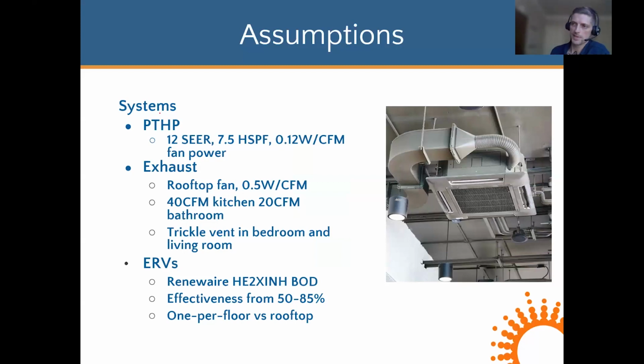And then we applied some systems assumptions. All of the apartments had package terminal heat pumps, with ASHRAE 90.1 2016 minimum efficiency levels in fan power. For the exhaust-only scenario, we looked at a rooftop exhaust using fan power from similar projects of similar size and design. Trickle vents were the makeup air source for the exhaust-only scenario in both the bedroom and the living room. And for the ERV scenario, we used the basis of design of Renew Air HE2 model with effectiveness ranges from 50 to 85%. And we also looked at 1 per floor ERVs versus a rooftop ERV unit.